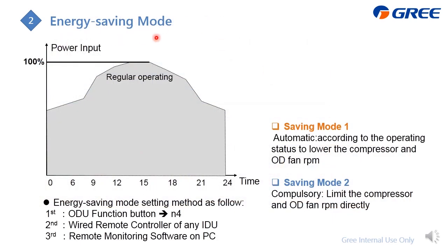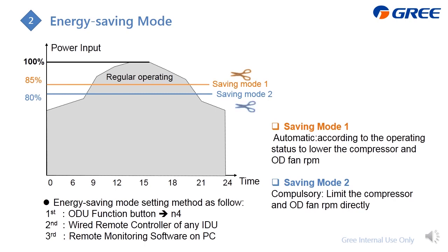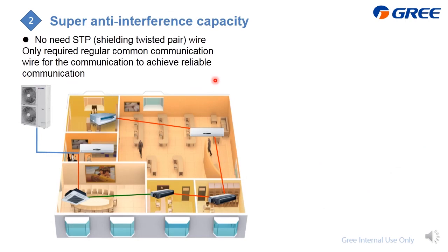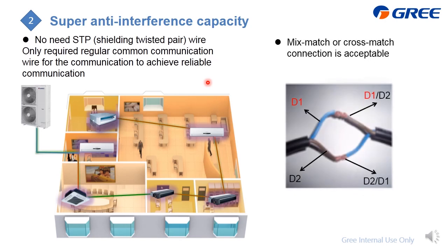Energy saving mode is also the same as the GMV heat pump regular, so we can skip. As the system adopts the CAN communication technology, the communication speed is very fast, and also we don't require the STP, just the regular 2 wires is okay. And also the wire is non-polarity. That means for the wiring, you don't need to memorize the color of the wires, just mix match and cross match is acceptable.